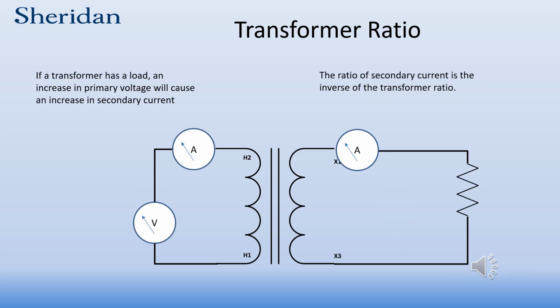Okay, so if we look at transformer ratio with respect to current, if a transformer has a load, in other words, connected to the secondary winding is a path for current to flow, an increase in the primary voltage will cause an increase in the secondary current. You have to remember that the load is what determines how much current is going to flow, or how much load is applied to the transformer. The ratio of the secondary current is the inverse of the transformer ratio that we had for voltage.